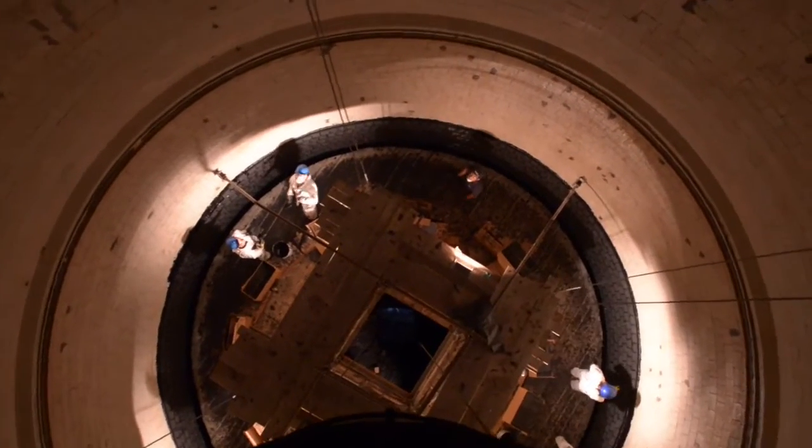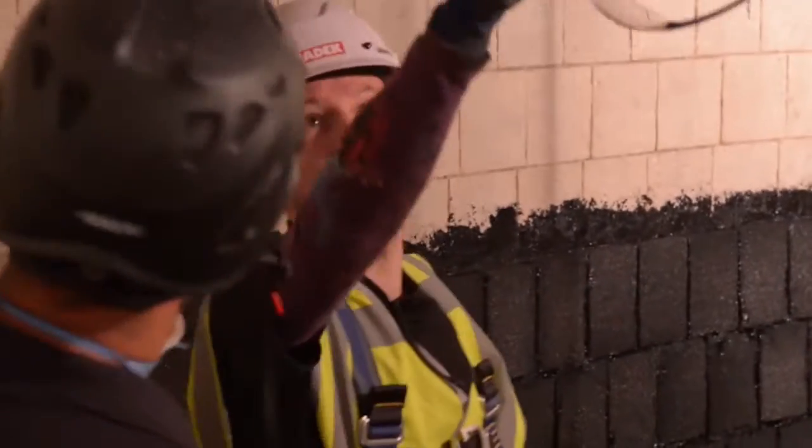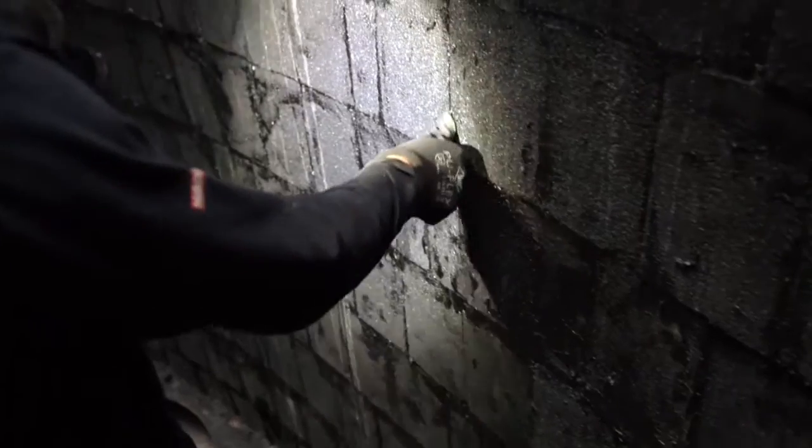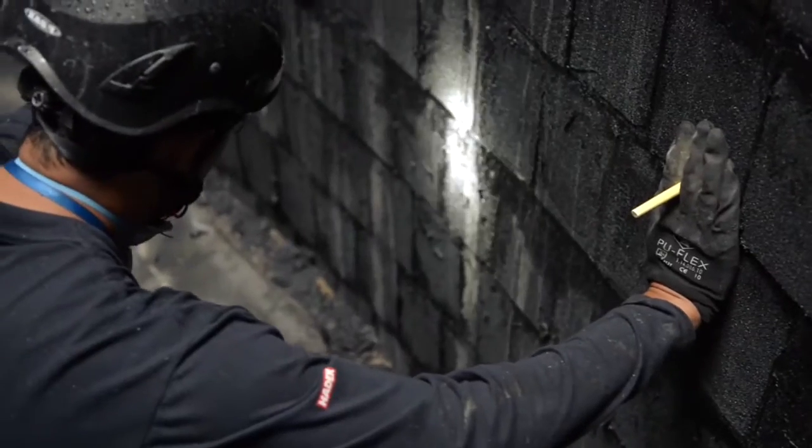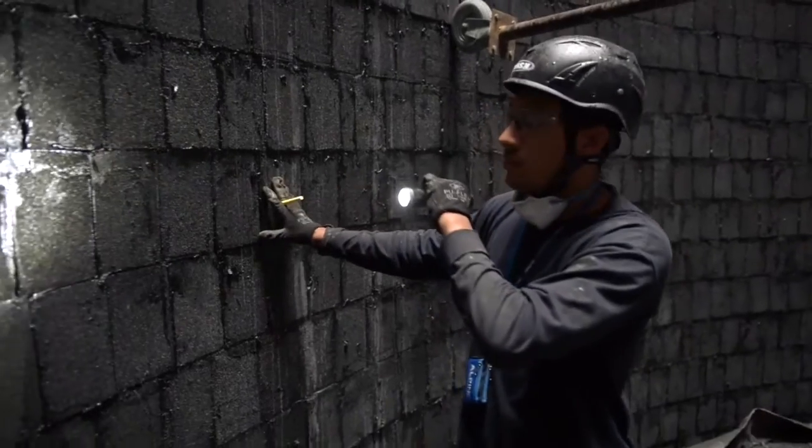It acts as a thermal insulator, which reduces the amount of thermal condensation within the liner. It also provides a surface which is very favorable for wet operation because it minimizes the potential for droplet reentrainment back into the gas flow.